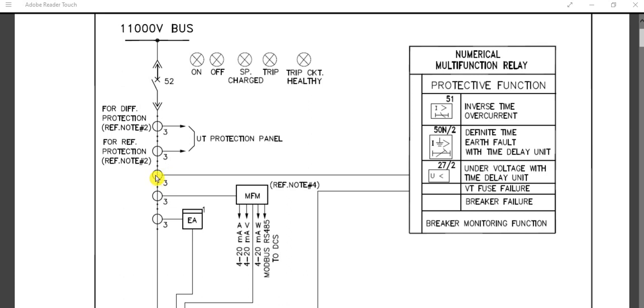The third CT is connected to the main numerical multi-function relay, which provides protection for this particular feeder. This numerical multi-function relay performs several protection functions. The features include relay functions 51, which as you know is inverse time overcurrent — basically inverse time phase overcurrent with IDMT characteristic.